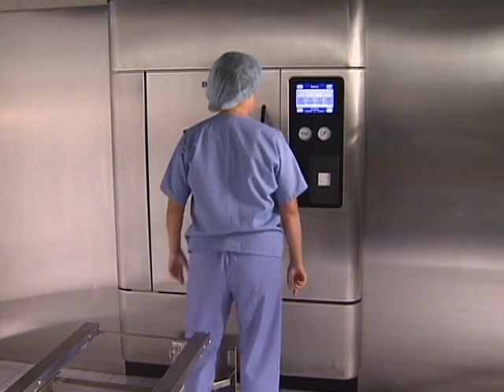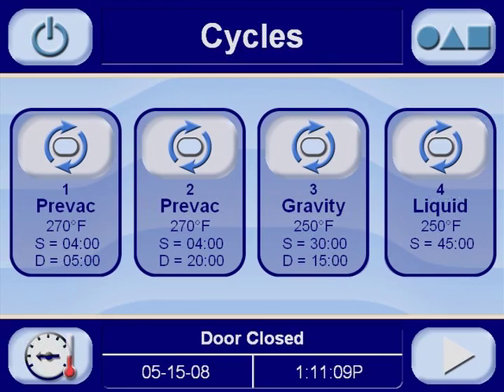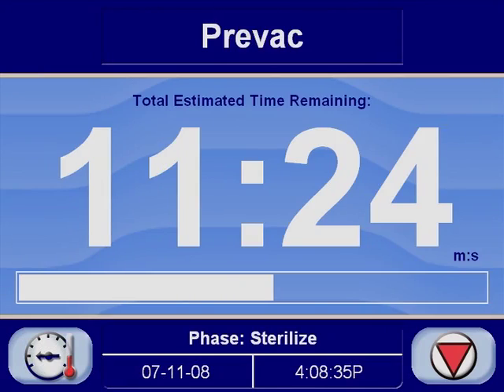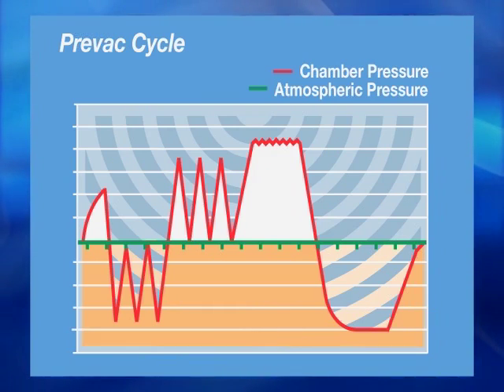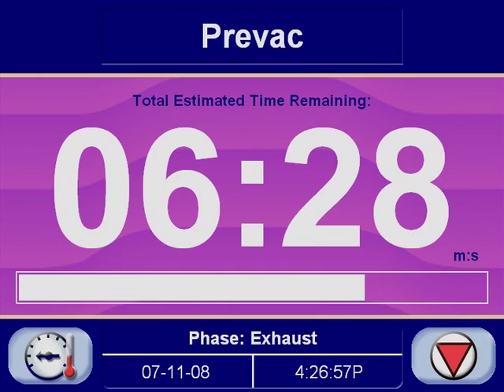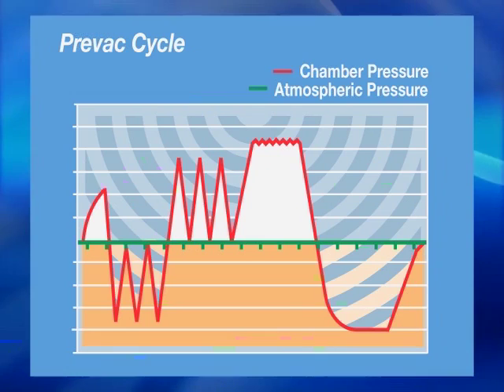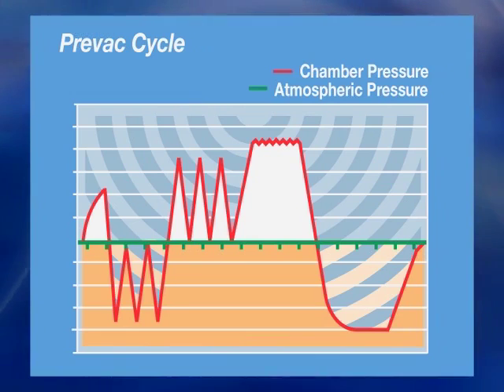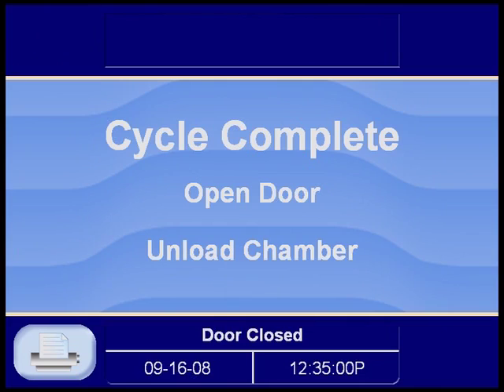At the beginning of the cycle, the chamber is purged with steam and the load is conditioned. When the chamber reaches sterilization temperature, the sterilization phase begins. Once the sterilization phase is completed, an exhaust and dry phase begins. The control panel displays the dry time remaining in the cycle. When the cycle ends, the chamber is returned to atmospheric pressure, and a vacuum is drawn on the seal, retracting it from the inner surface of the door. Then you will hear the Cycle Complete tone. The display screen indicates that the cycle is complete and instructs you to open the door and unload the chamber.